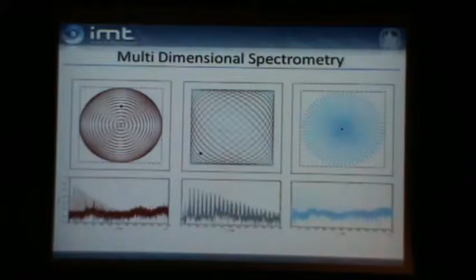And what you see is then that for the spiral, for example, where we have almost a rotational change of the magnetization, the rotation speed is so fast that the particle cannot follow in terms of Brownian rotation, and this damps the signal. So the signal decay is much faster than, for example, in this radial excitation. And the Lissajous that a lot of us are using for our scanners is a mixed case of both. And it is very complicated where the particle is and what the particle sees as a type of reaction to the excitation. But this can be studied with our new kind of spectrometry, and there we are today in this line of instrumentation.